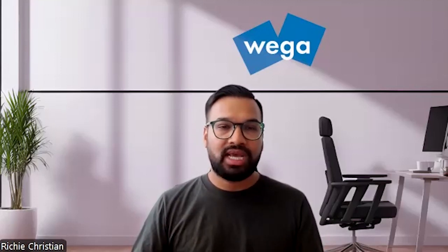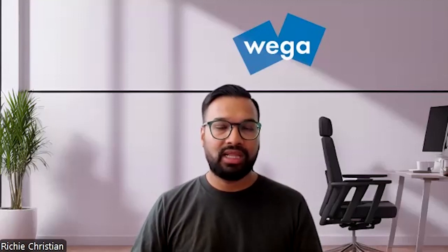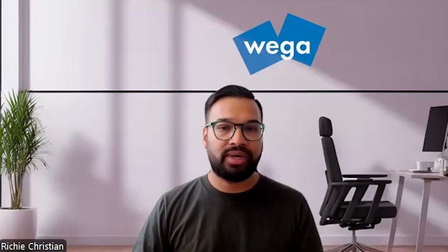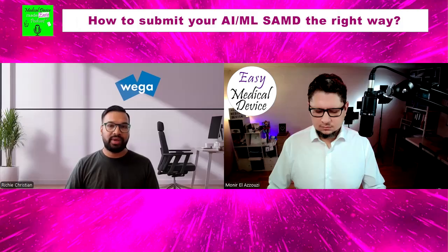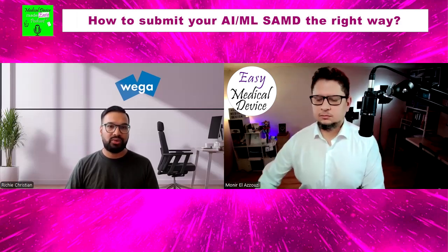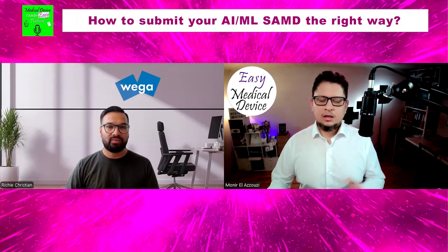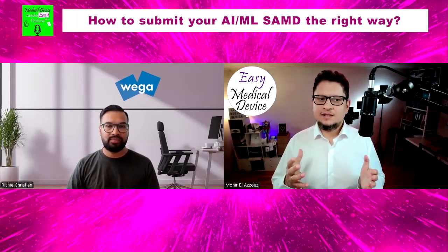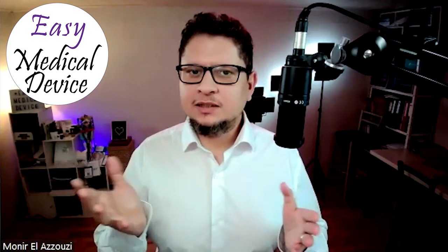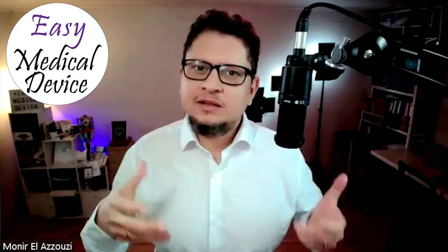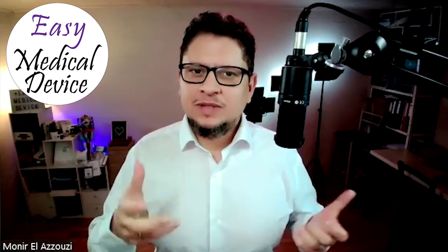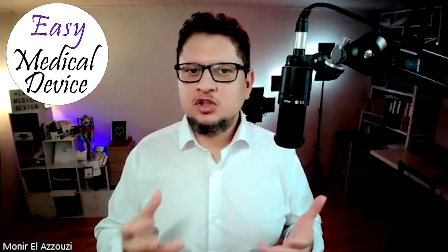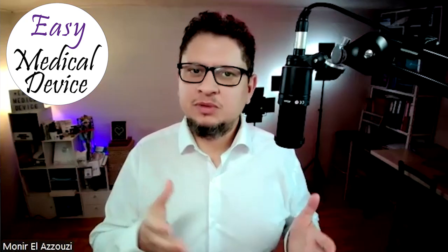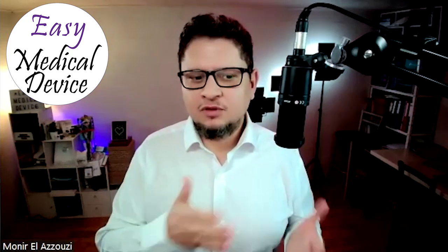So there are all of these scenarios in which these types of devices fall, and it's really important to tell the reviewers and the regulators, in the software description for example, to say: this is the end-to-end clinical workflow, this is where our device fits in, and this is exactly what it attempts to do in that workflow. So for the regulators, the idea is that you have to describe it clearly and put them into experience mode, to tell them here is how it will be working from A to Z. It should not be theoretical or conceptual. It should be the real-life process or workflow.